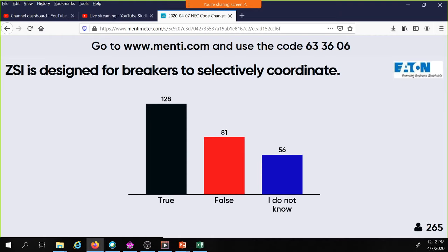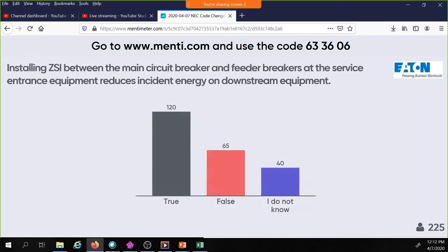If you do not set your overcurrent protective devices with their set points, you're not going to get selective coordination just because you have ZSI. If your fault current is higher than the instantaneous pickup of both of those devices, you're not going to get selective coordination because of ZSI. So we're going to have fun with that one as we move through it.